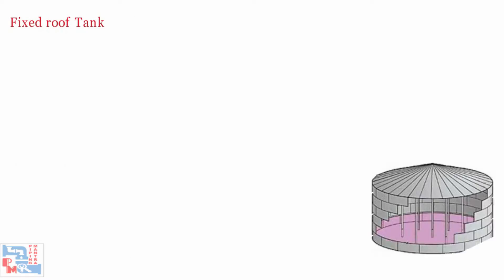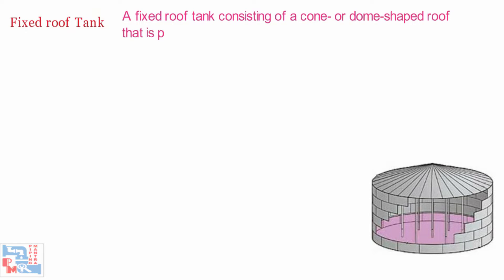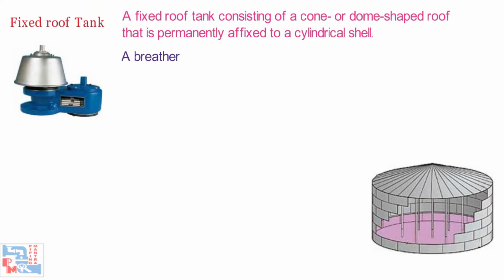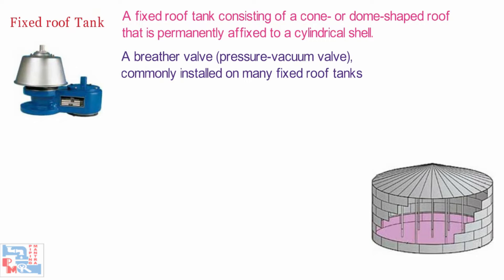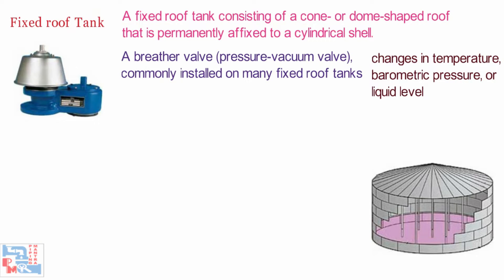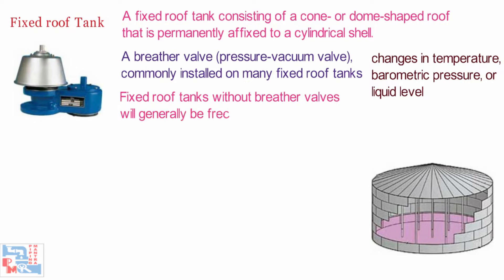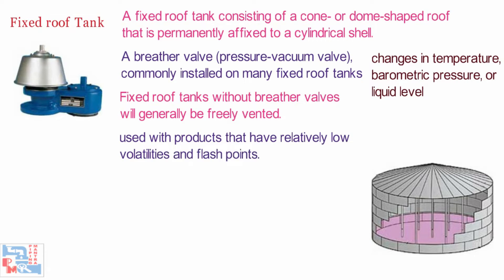Next is the Fixed Roof Tank — a fixed roof tank consisting of a cone or dome-shaped roof that is permanently affixed to a cylindrical shell. A breather valve, that is a pressure-vacuum valve, commonly installed on many fixed roof tanks, prevents the release of vapors during very small changes in temperature, barometric pressure, or liquid level. Fixed roof tanks without breather valves will generally be freely vented. Fixed roof tanks are typically used with products that have relatively low volatilities and flashpoints.